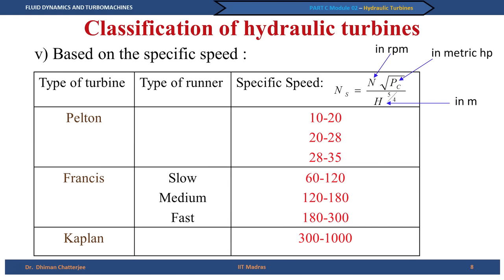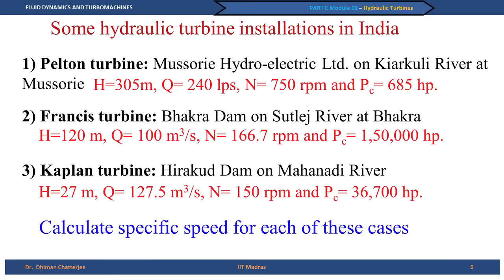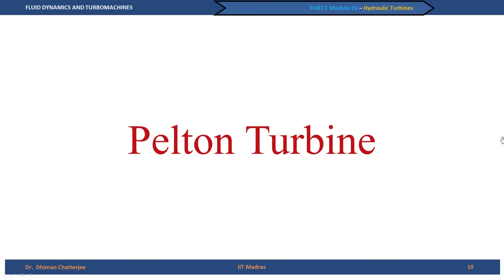You may ask: what is wrong with using a Pelton turbine at a specific speed in the range of 120 to 180? The reason is that you will not get the best efficiency. We are talking about using a particular type of turbine where the efficiency should be highest. For example, Pelton turbines are seen in the Mussorie hydroelectric power plant, Francis turbines in the Bhakra dam, and Kaplan turbines in the Hirakud dam in India.